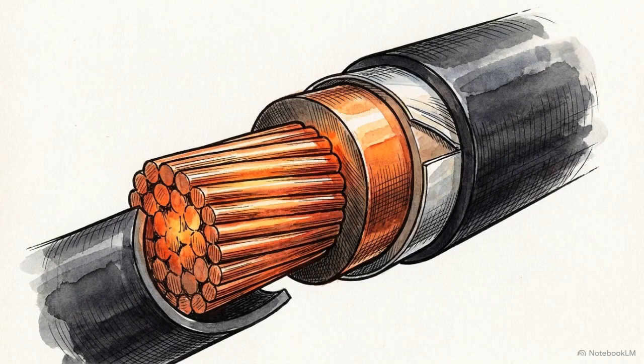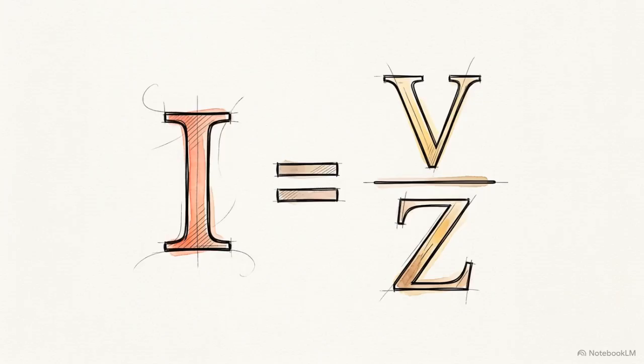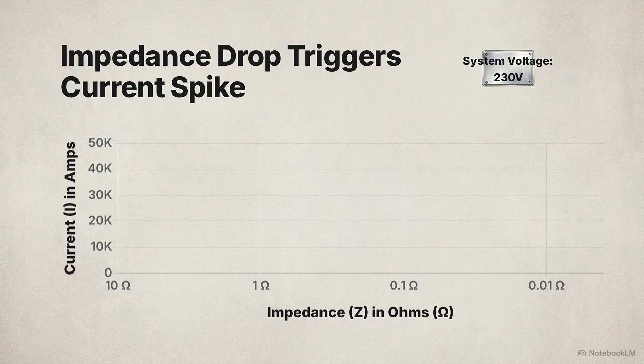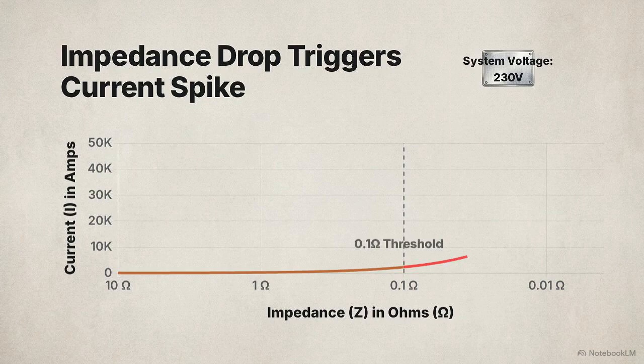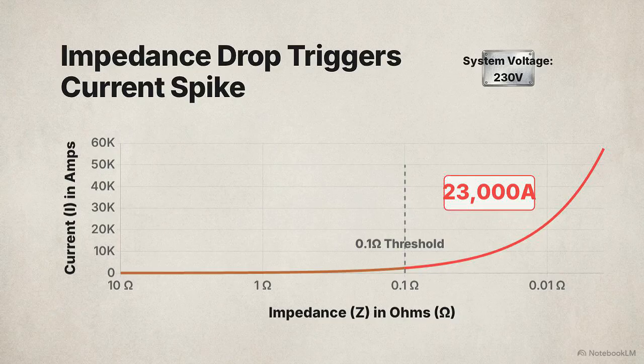As the current travels away from the transformer, the physical resistance of the copper conductors acts as a massive braking system on the fault energy. This is dictated by alternating current Ohm's law, where current equals voltage divided by the total circuit impedance. This graph plots fault current against decreasing circuit impedance at 230 volts. Notice the nonlinear relationship. As impedance drops below 0.1 ohms, current spikes violently upward. At 0.01 ohms, a standard industrial value, the current explodes to 23,000 amps.